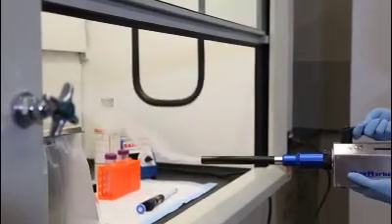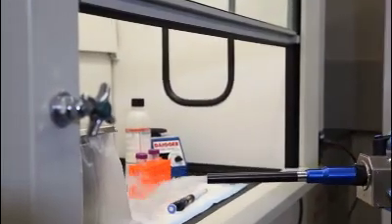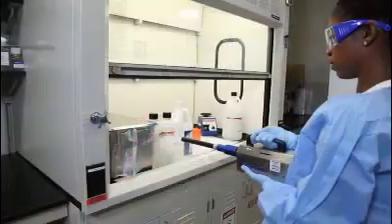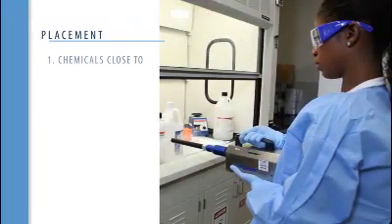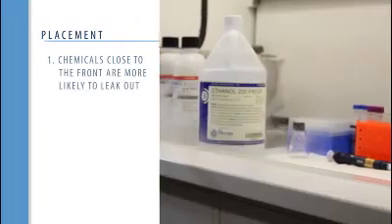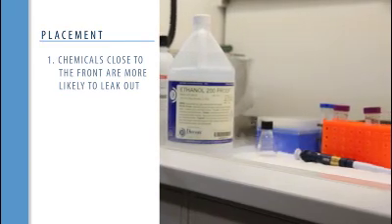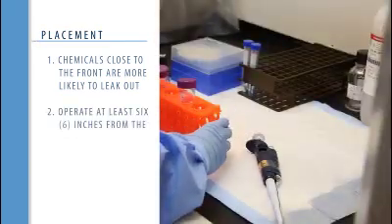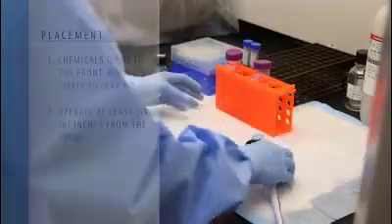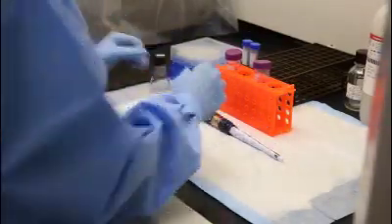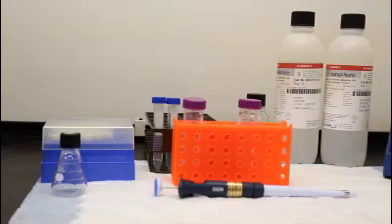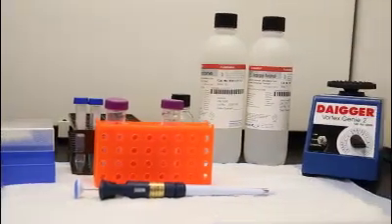Many conditions can affect the efficiency and safe operation of a fume hood. Chemicals closer to the front of the hood are more likely to leak from the hood. Operate at least six inches from the front. The placement of objects close to the front opening may result in leakage and loss of containment.